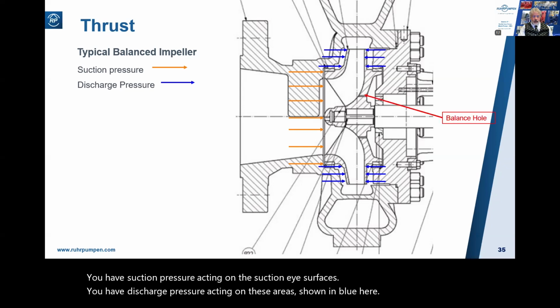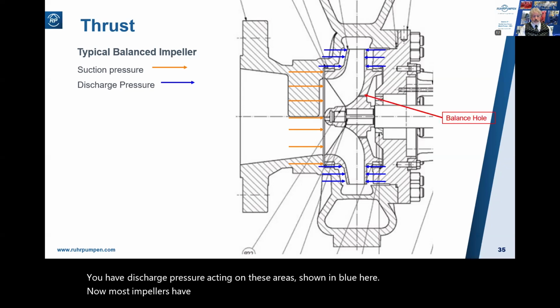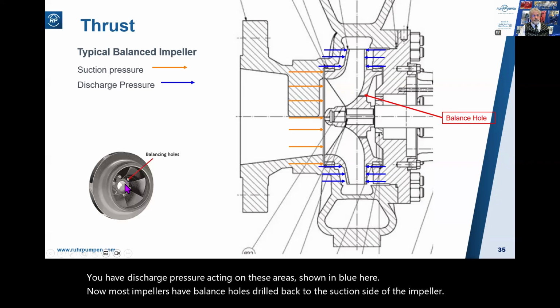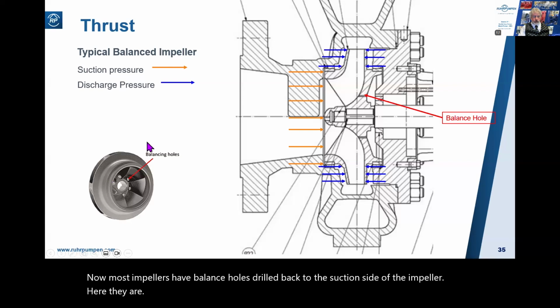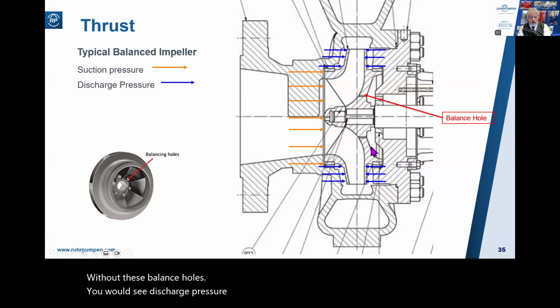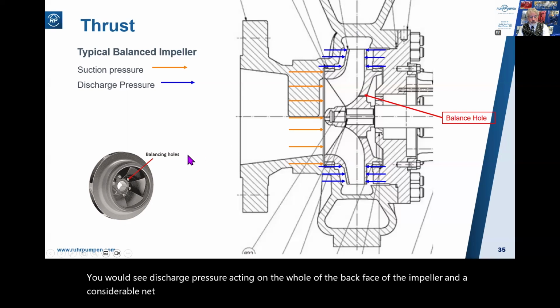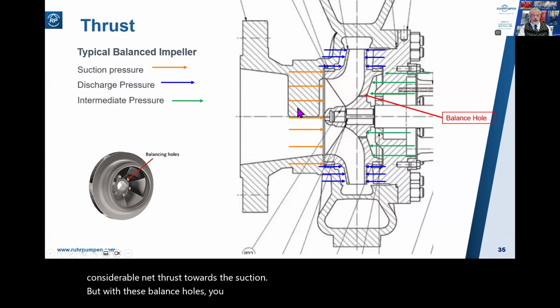Now, most impellers have balance holes drilled back to the suction side of the impeller. Here they are. Without these balance holes, you would see discharge pressure acting on the whole of the back face of the impeller and a considerable net thrust towards the suction. But with these balance holes, you get a pressure breakdown across the wear rings and back through the balance hole.